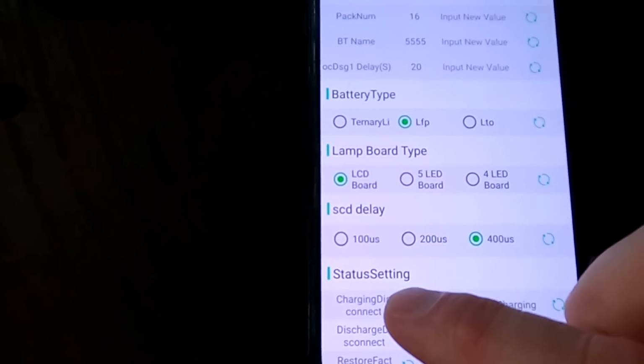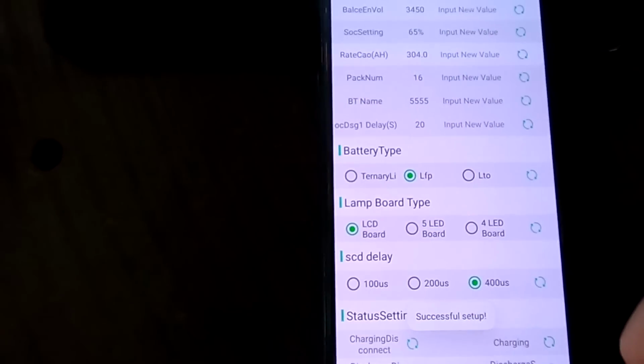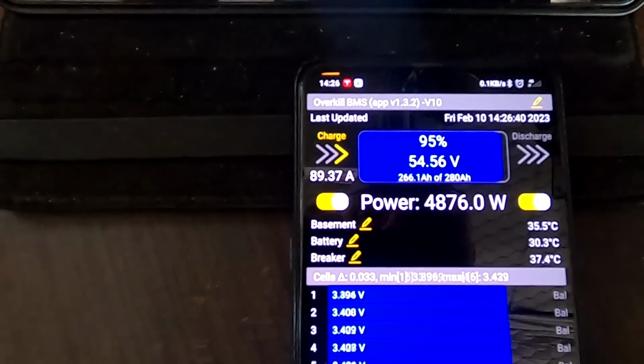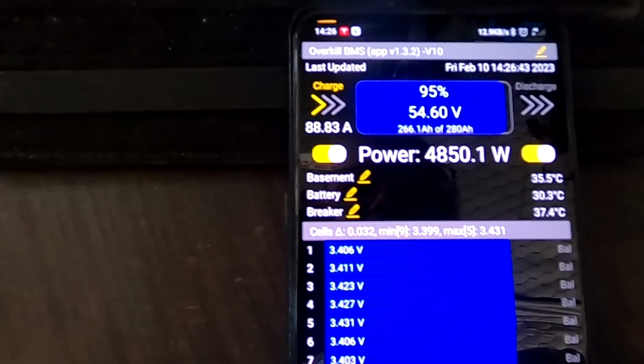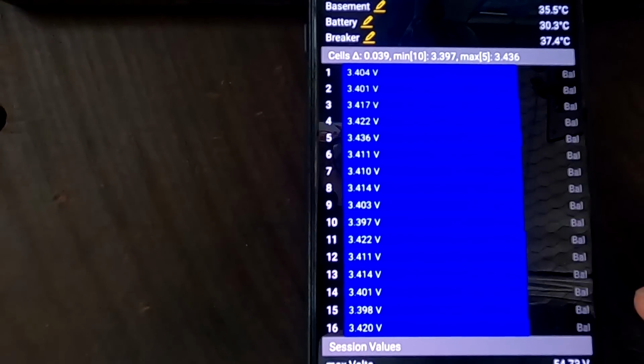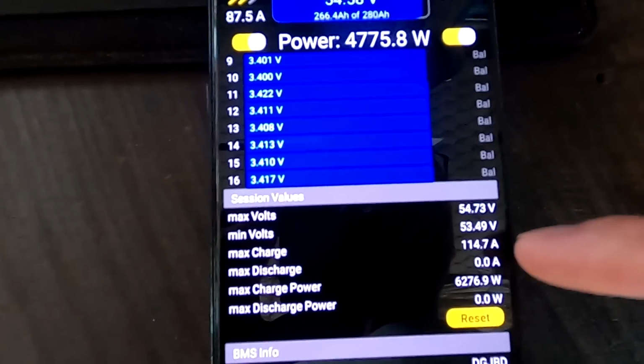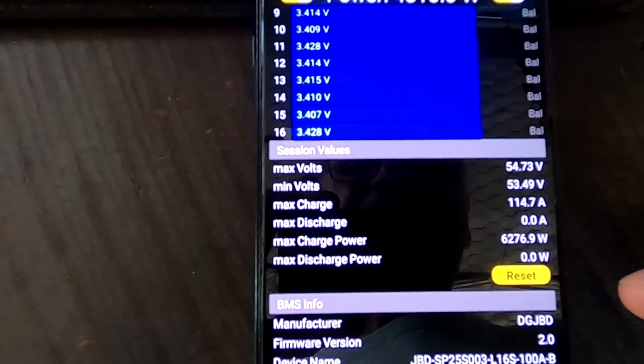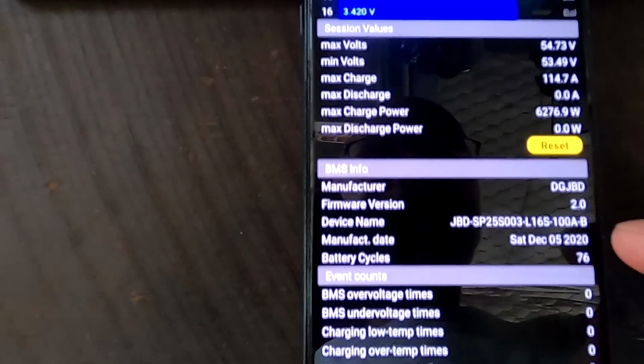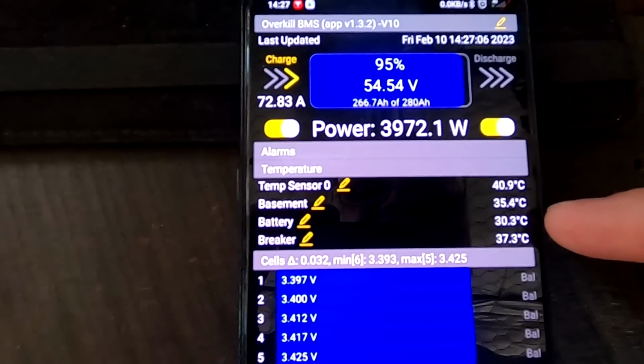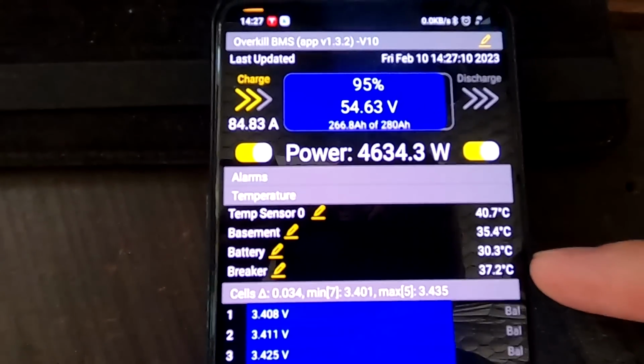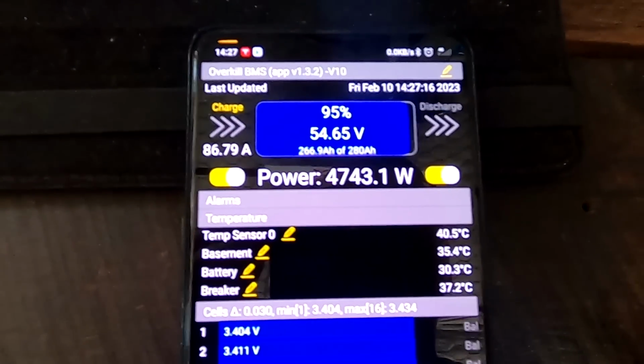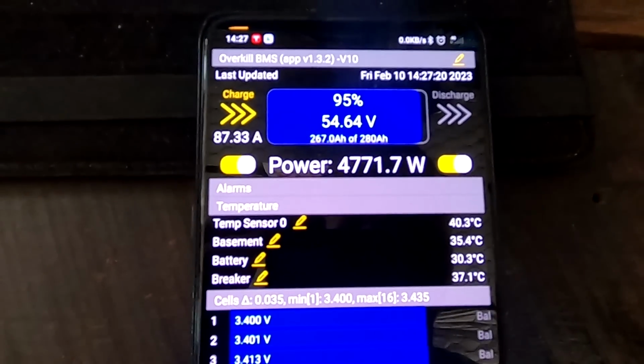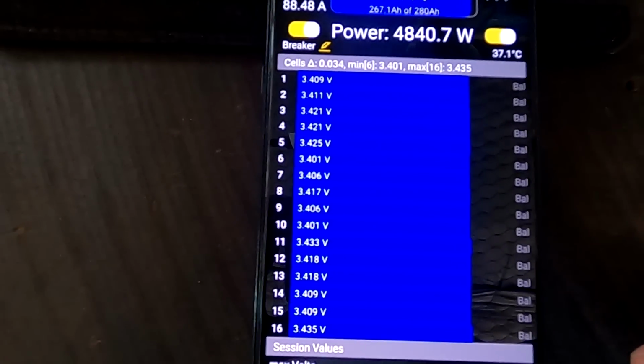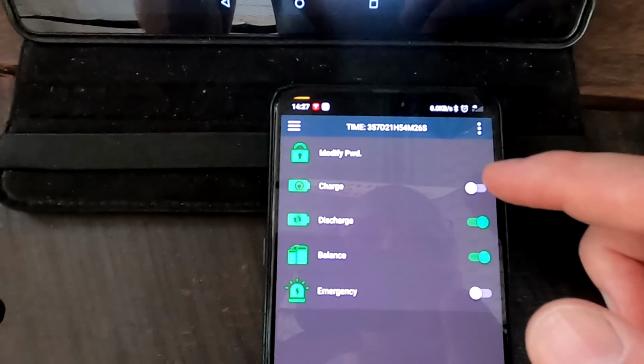And now the Heltec BMS has turned on again. It is annoying. Okay. Success. Okay, we are back to 90 amps. And deviation looks actually pretty good. There's no balancing so far. We have seen 114.7 amps since we are connected. 6.2 kilowatts into the battery. And the temperatures are 35, 30, 37 in the breaker. So the breaker of course will heat up now because we are hitting the rated current of the circuit breaker. But yeah, so far I cannot see any issues here with this BMS either. Okay, let's turn on the JK again.